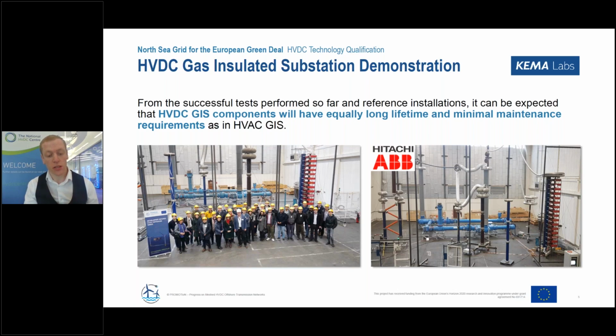You can see in the pictures the test setup that was used. The bus bar arrangement itself isn't something you'd expect to actually realise, but the DC test rig was there to include all the key components - bus duct, disconnectors, earth switches, bushings, VTs, and everything you'd expect to find, but not necessarily in the arrangement used. The nominal rating of the equipment was 320 kV.